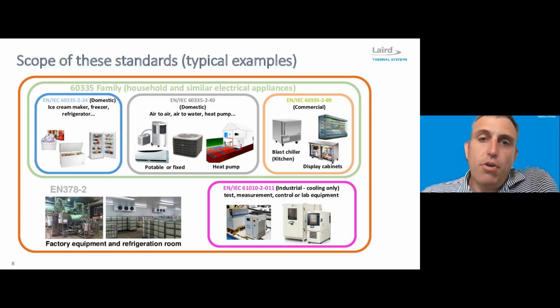Just to give you a visual of some of the products, this is the same type of image that I showed on the previous slide, just with actual products. So you can see 60335 is the household or similar type of equipment that is presenting standards for refrigeration use, heat pumps, freezer displays, and then in the lower right here, I show some more industrial equipment or laboratory equipment under which the cooling systems tend to apply. That then has requirements that kind of fall back on this EN 378 refrigeration standard.